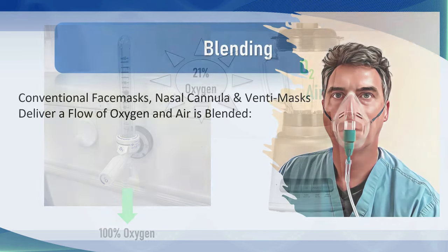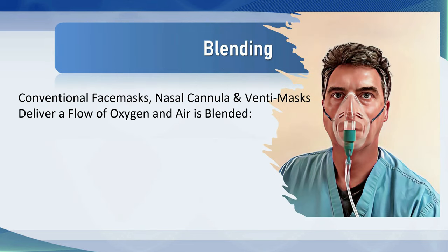When you place a patient on a mechanical ventilator and dial up an FiO2 between 21% and 100%, you don't usually consider how the ventilator manages to deliver that exact FiO2. What it has inside is a blender — it mixes the oxygen and air together and precisely controls the output. Conventional face masks, nasal cannulae, and venti masks also deliver a flow of oxygen that is blended — in the airway in the case of nasal cannulae, in the mask and airway with simple face masks, and in the Venturi device with venti masks.